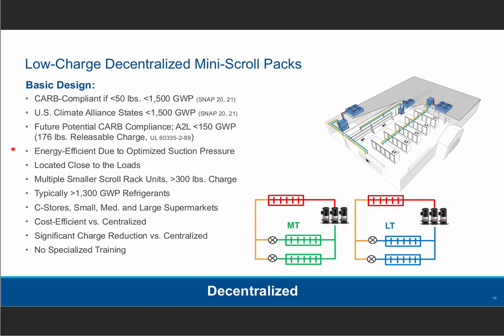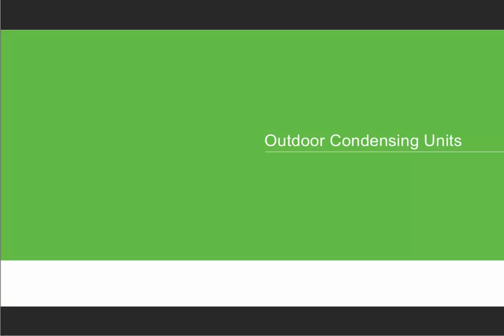So that's interesting. I talked about optimized suction pressures. Some of these smaller racks can have some different charge limits, of course. They typically use refrigerants now around 1300 GWP, or those that are available that meet the SNAP regulations. C-stores, small to medium, and even large supermarkets use these. And really no specialized training is required because it's kind of a known entity. So that's one architecture that we're looking at.